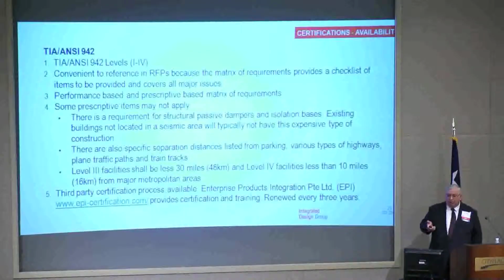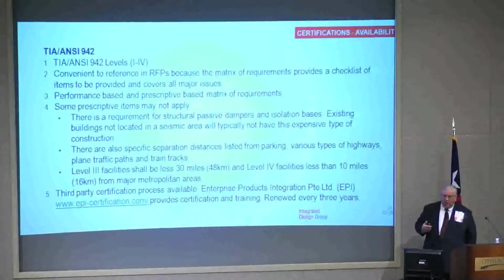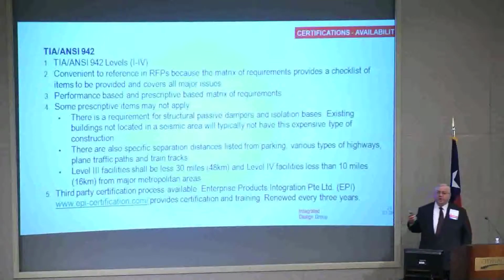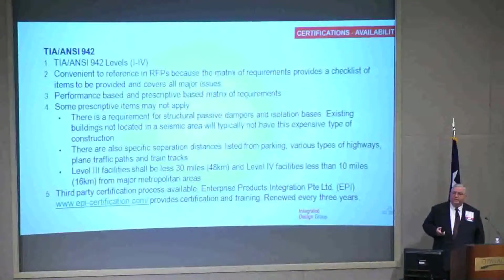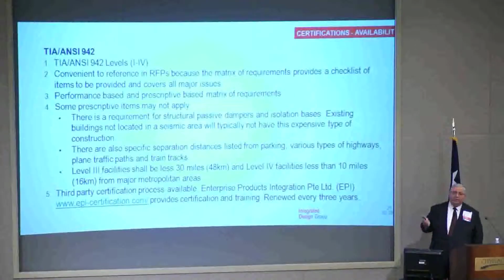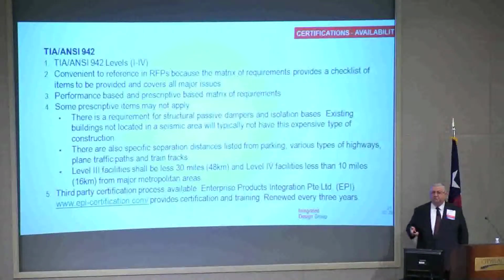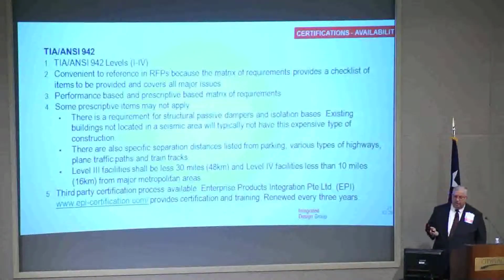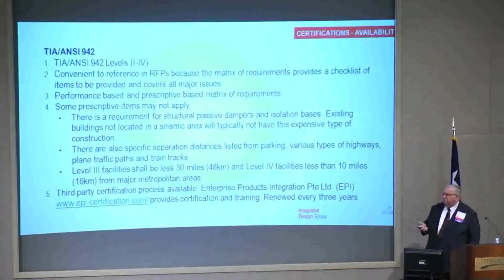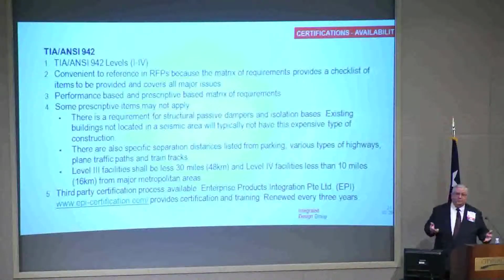One example is they have a requirement for structural passive dampers and isolation bases on a Tier 3 design, regardless of whether you're in a seismic area or not. It's a checklist requirement, so unless you're in California or a high seismic area, you don't see that requirement. So an existing building won't have it.